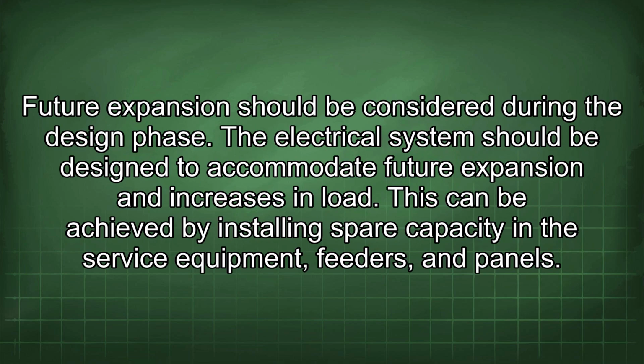Future expansion should be considered during the design phase. The electrical system should be designed to accommodate future expansion and increases in load. This can be achieved by installing spare capacity in the service equipment, feeders, and panels.